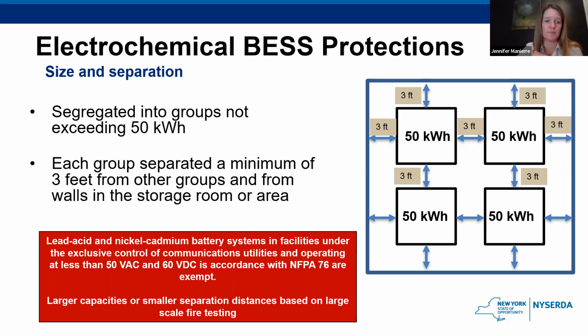But then finally, larger capacities. So you could have groups larger than 50 kilowatt hours or separation distances smaller than 3 feet if that large scale fire testing that we talked about earlier shows that it's safe to do so. This is one of those cases where the code official can grant an exemption based on the results of the large scale fire testing. Maybe you say up to 100 kilowatt hours per unit and 2-foot separation, just as a hypothetical example, if the large scale fire testing shows that that's safe to do and that a fire in one will not propagate to another.